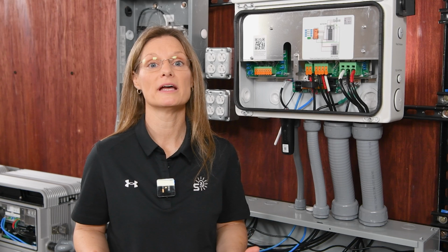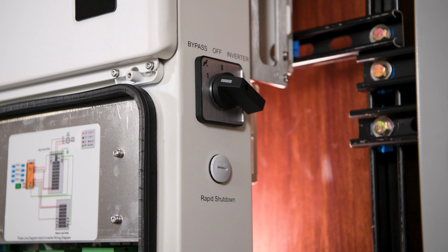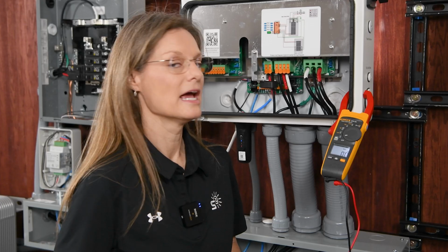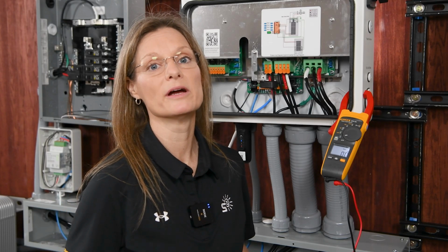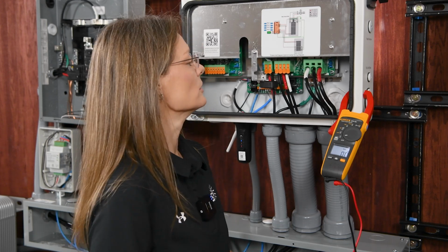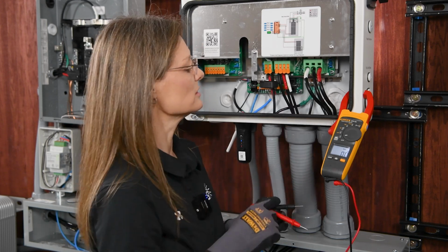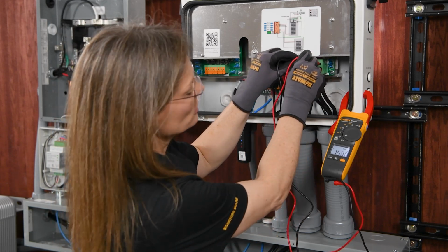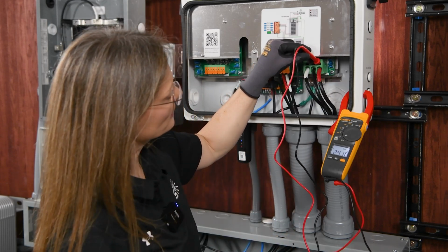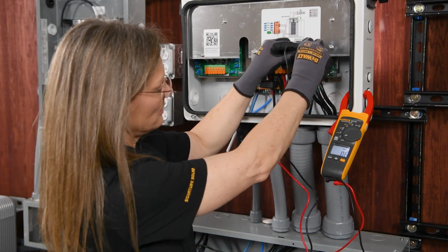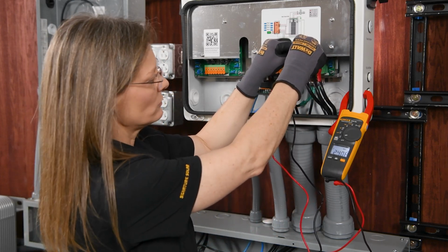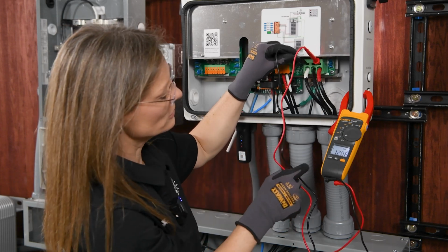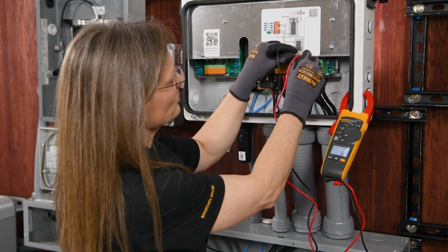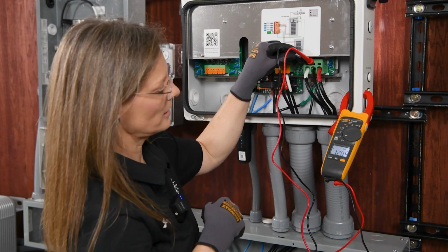The next step in our process is to go ahead and turn our inverter on, so we'll allow it to receive grid power. We'll turn our bypass switch over to bypass and we'll begin checking our voltages. As we begin checking the voltages, be aware you are working with live wires. We will be checking the voltages from line 1 to line 2. We're looking to see that we are getting 240 volts, and we're just checking right above these wires here. And we are reading 240 there. Then we'll check from line 2 to neutral. We are reading 120, and then from neutral to line 1, we're also getting 120 there.